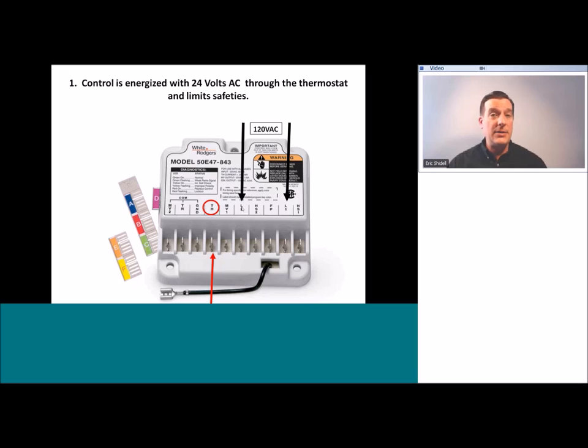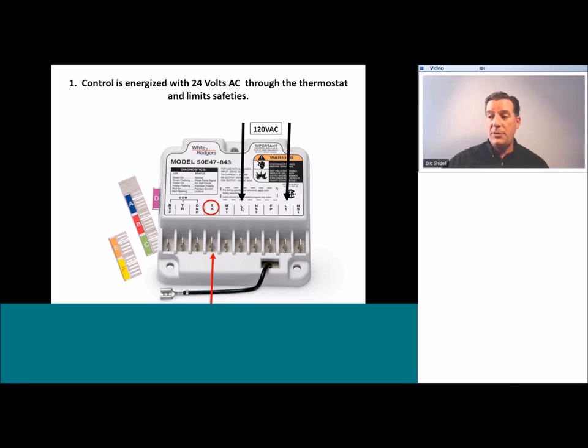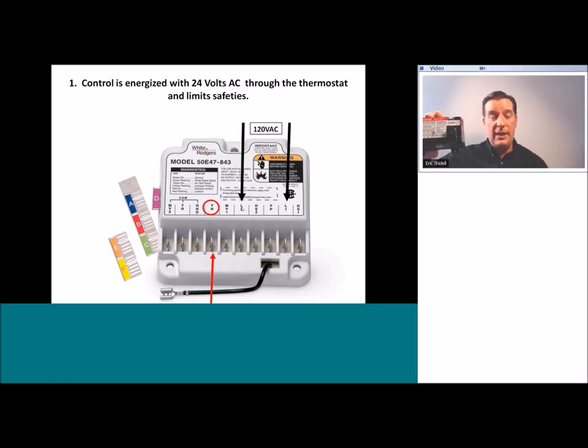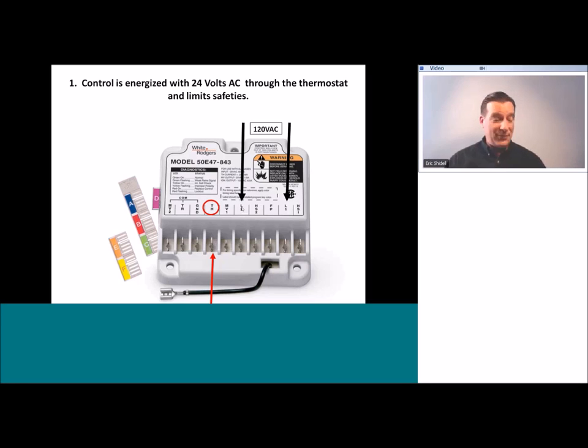The most common types of non-integrated HSI controllers are the White-Rodgers 50E47 and all of its variants in the White-Rodgers 50E series, and the Honeywell S8910U. The S8610U we've seen is for intermittent pilot; the S8910U looks almost exactly the same but is generally green.